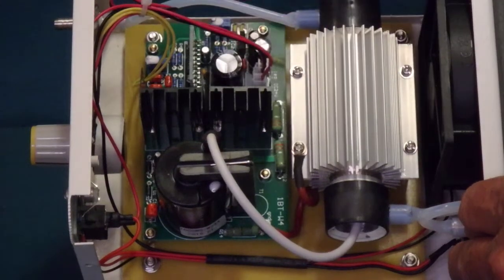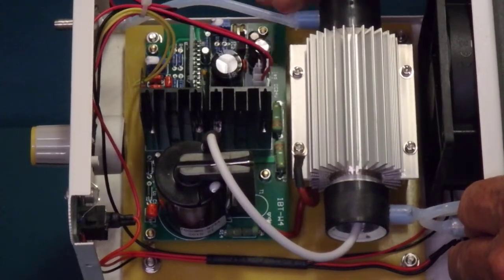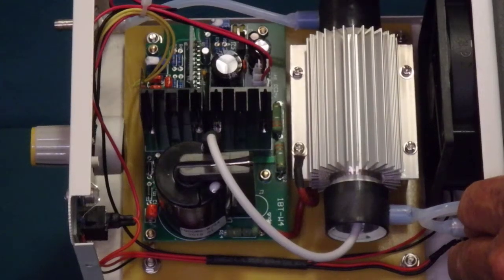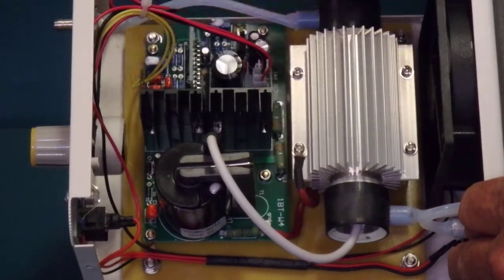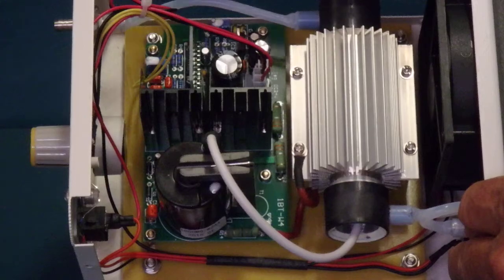It literally will outlast the electronics of the unit. In fact, these can be taken off and put on a new one. Teflon, there is no other material or tubing that is as durable as Teflon in the presence of ozone.